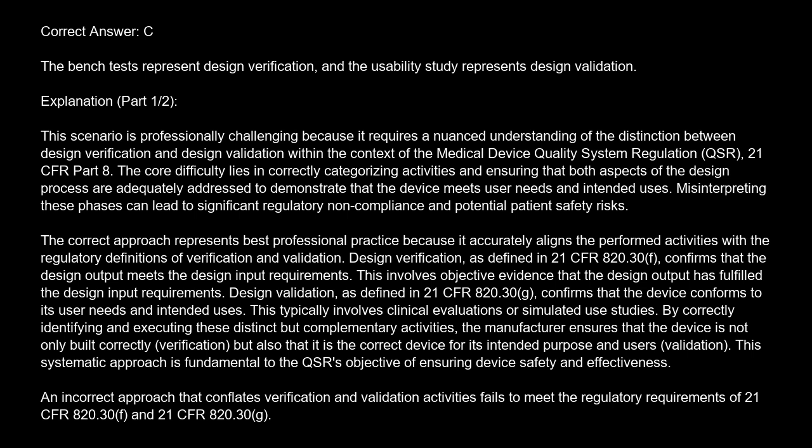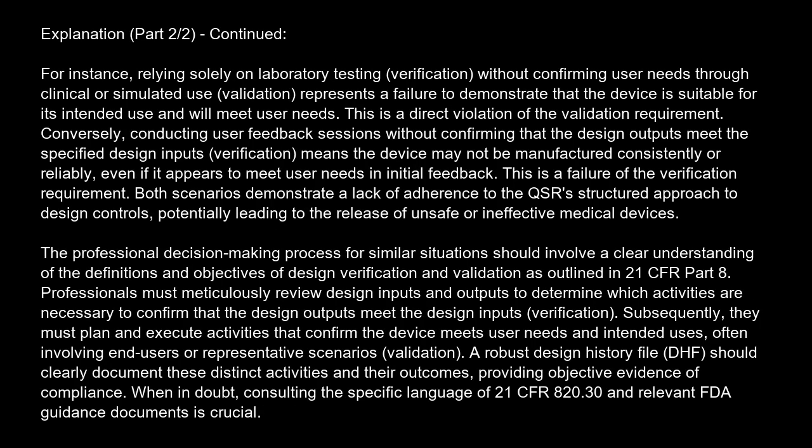An incorrect approach that conflates verification and validation activities fails to meet the regulatory requirements of 21 CFR 820.30(f) and 21 CFR 820.30(g). For instance, relying solely on laboratory testing (verification) without confirming user needs through clinical or simulated use (validation) represents a failure to demonstrate that the device is suitable for its intended use and will meet user needs. This is a direct violation of the validation requirement.